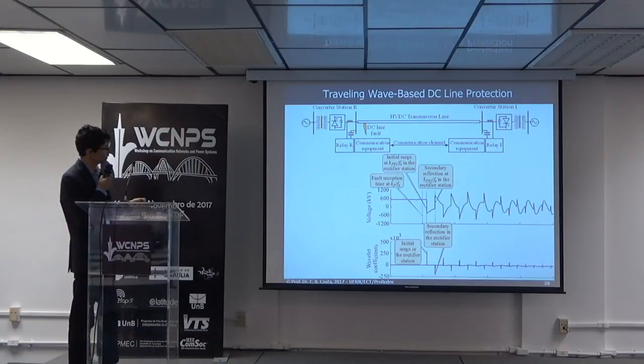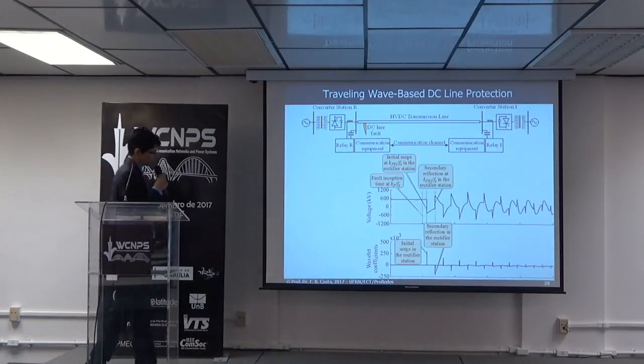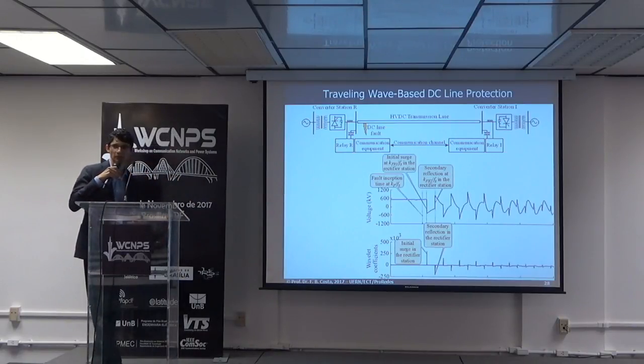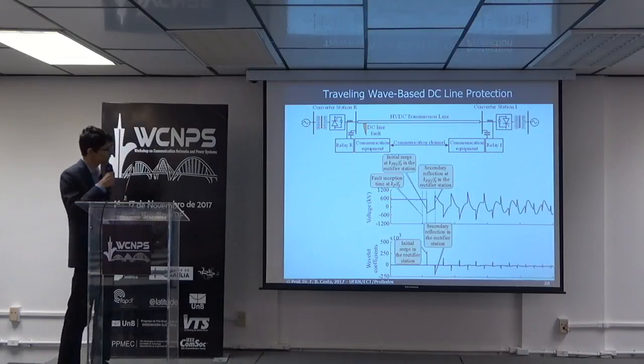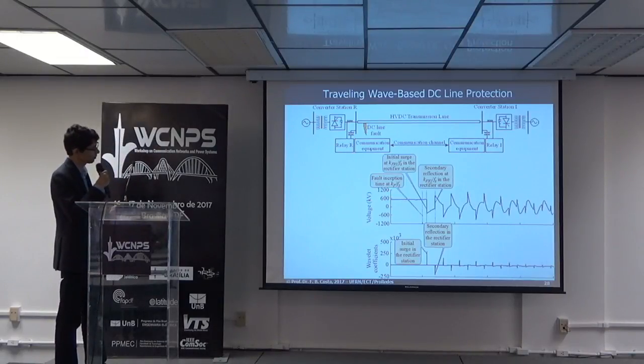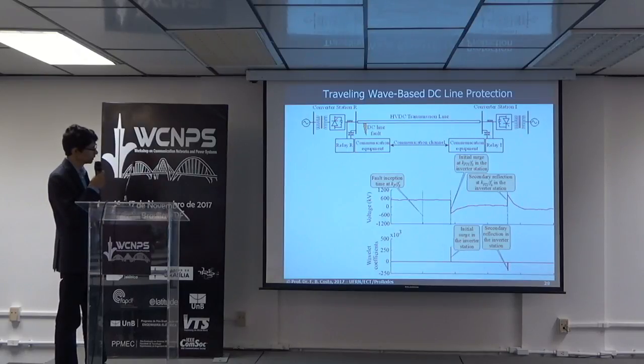Here is an HVDC power system, and in this example, it's possible to detect, by using the wavelet transform, the surge time incidence, and it's possible to locate the fault with a high precision, with a high accuracy, and it's possible to perform a high-speed protection. Here is the protection in this converter station.